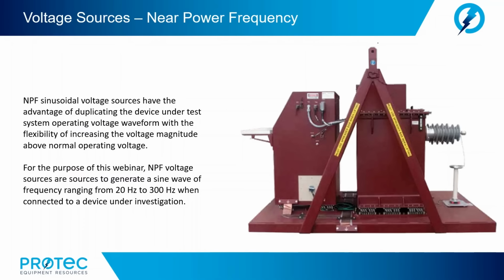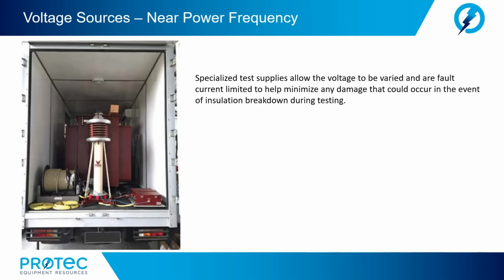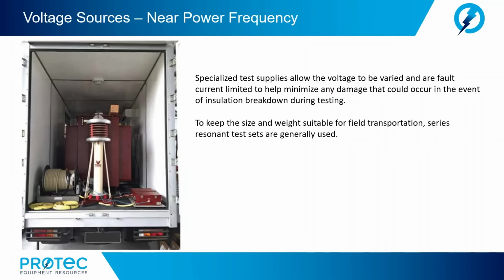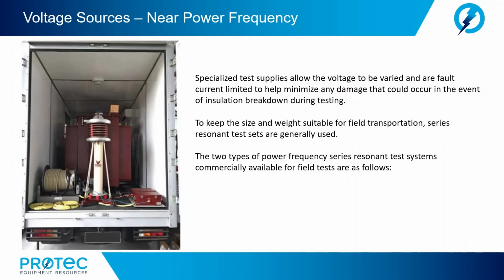Now, for the purpose of this webinar, near power frequency voltage sources are sources that generate a sine wave of frequency ranging from 20 Hz out to about 300 Hz when connected to a device under investigation. Specialized test supplies allow the voltage to be varied and are fault current limited to help minimize any damage that could occur in the event of insulation breakdown during testing. To keep the size and weight suitable for field transportation, series resonant test sets are generally used. The two types of power frequency series resonant test systems commercially available for field tests are as follows. We have the frequency-tuned resonant circuits, or FTRCs, and we have the inductively tuned resonant circuits, or the ITRCs.